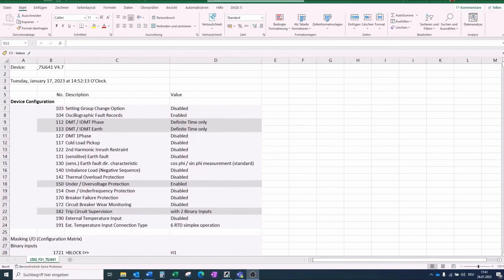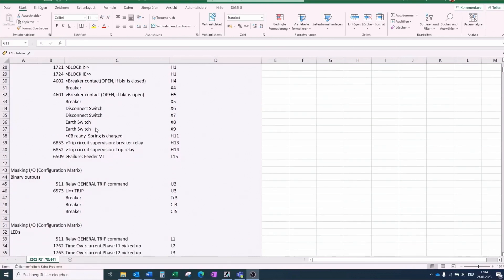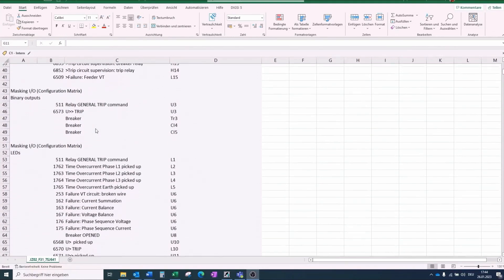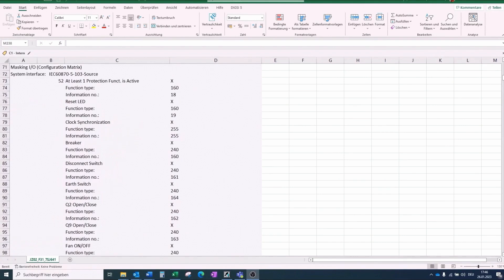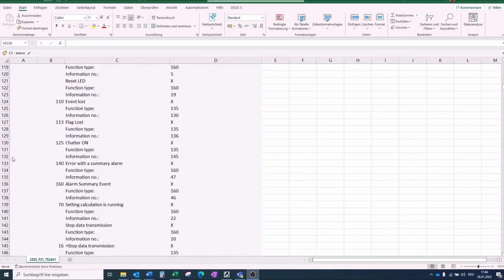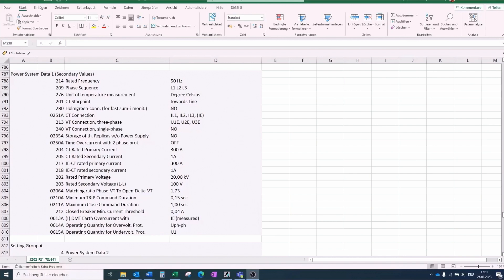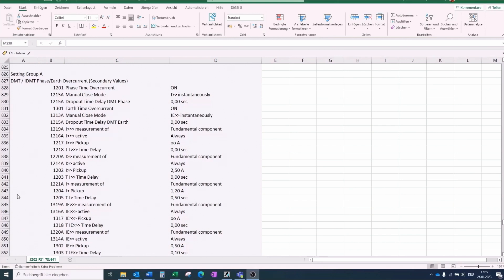The following information from the Excel file is of interest for the SIPROTEC 5 configuration in DIGSI 5. This is the device configuration. The masking I/O of binary inputs, binary outputs, and LEDs. The masking I/O interface for IEC 60870-5-103 protocol, source and destination. The power system data 1, which contains the CT and VT ratio and CT and VT connection properties. The setting group A, which contains the setting parameters of the function activated in the 7SJ641 device.